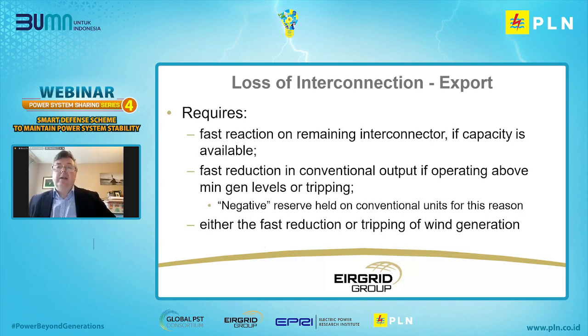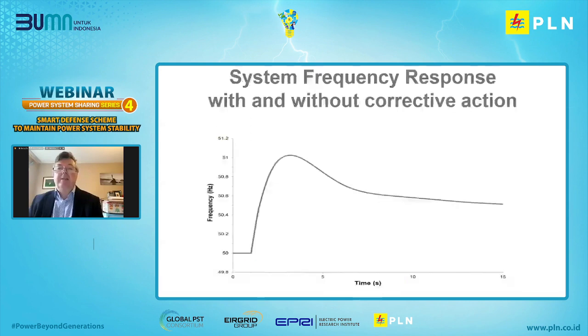Okay, so to manage this, it requires a fast reaction on the remaining interconnector if capacity is available, to either increase export if that's possible, or a fast reduction of conventional plants if operating above their minimum generation levels, or tripping them. So negative reserve is held at times on conventional plants for this reason. And then either the fast reduction or the tripping of wind generation. Okay, next slide, please.